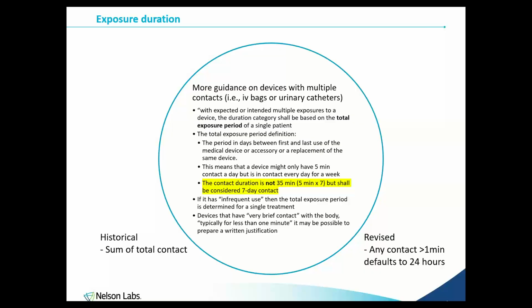The majority of our clients did it that way. The standard now says that you can't do that. So basically, regardless of time, one contact is a day. So in this scenario where you have everyday contact for 7 days, it would be 7 days contact, and so it would be a prolonged contacting device.